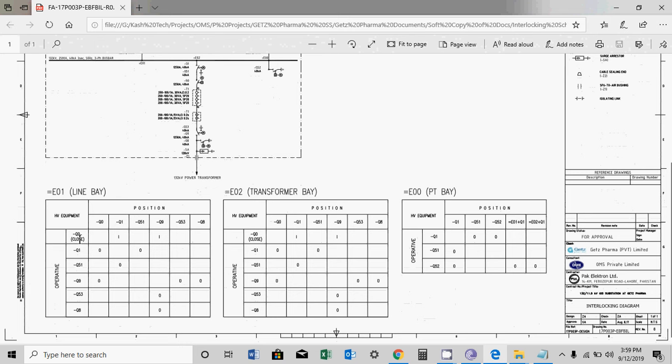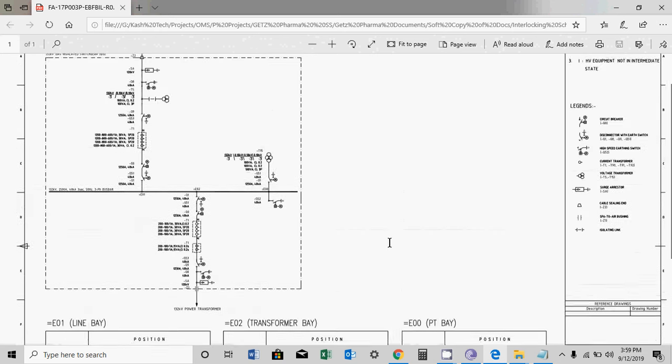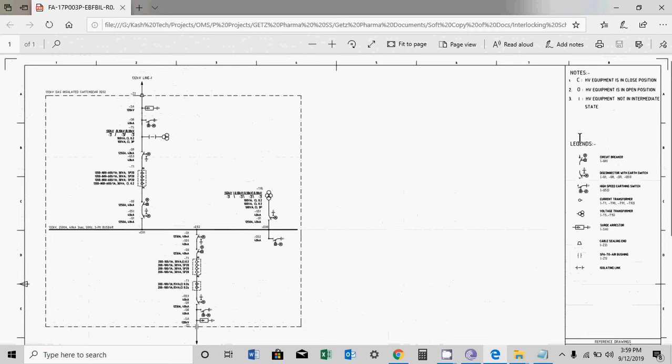So here you can see, you can close the breaker only if Q1 and Q9, any of them is on. If intermediate, you cannot close the breaker. So this is the first interlock we will see here. The symbols meaning: C means equipment is in closed position, O means equipment is in open position, I means equipment is in intermediate state.